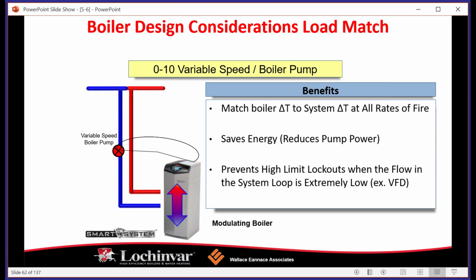So again, if you have 1 million BTUs and you have a 10-to-1 turndown, you can go down to 100,000 BTUs. Because do you need to run full boiler input every time the boiler comes on? The answer is absolutely not. You don't want to turn the boiler on, pump 1 million BTUs of energy into your system, and then turn it right off.